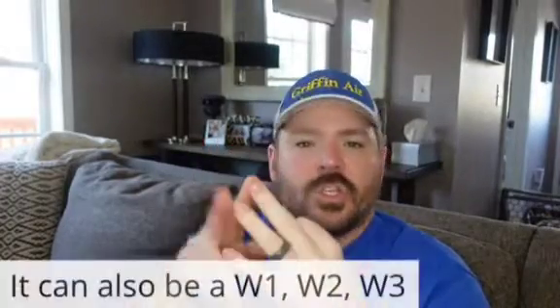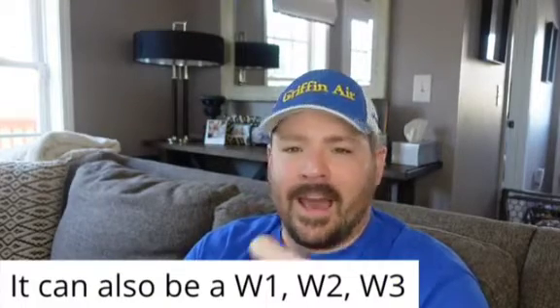Number two, a lot of thermostats have some sort of auxiliary heat. Sometimes they have multiple terminals, an AUX, an E for emergency heat, sometimes even three different ones, the third being like a W1, W2. A lot of thermostats are all-in-one anyway, but keep in mind, even if your thermostat has two or all three of those, your system itself might only have one backup heat source or one stage of backup heat. So with a lot of those thermostats we'll actually end up adding a jumper in there. So if I've got an AUX and an E, whether I put that thermostat in emergency heat or regular heat, I want it to still bring on those backup heat strips, whatever that backup source is, so I jumper those two, that way it still controls that one backup heat source.